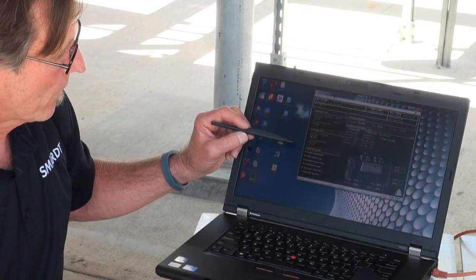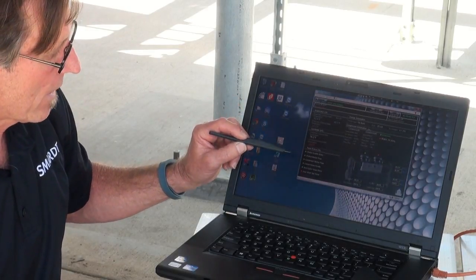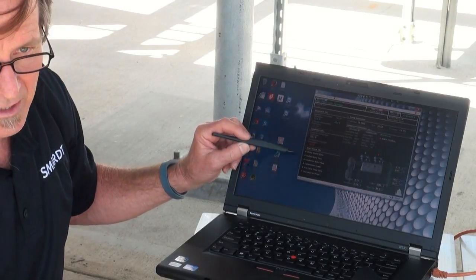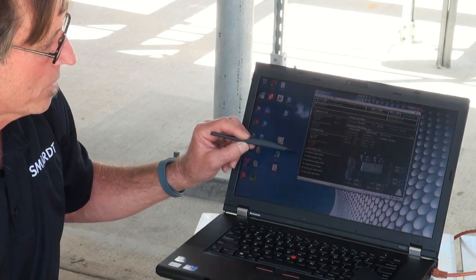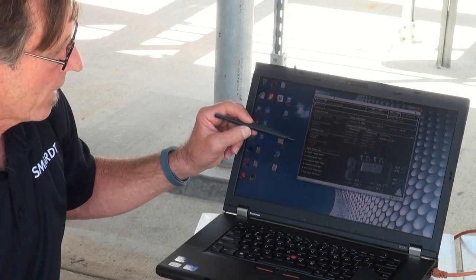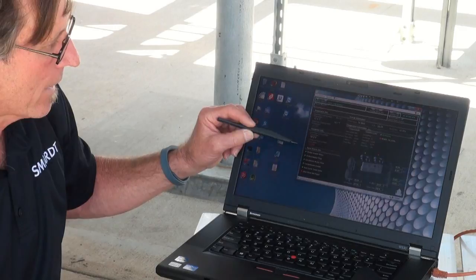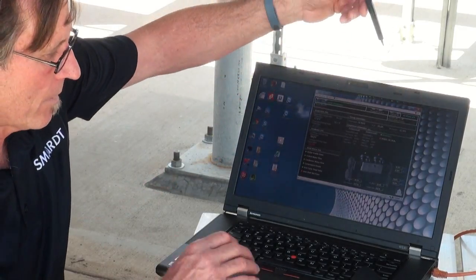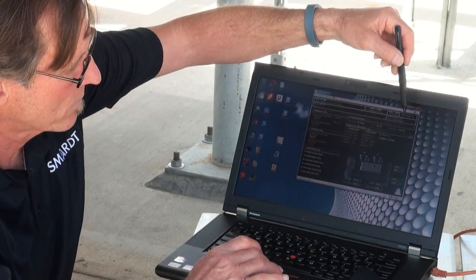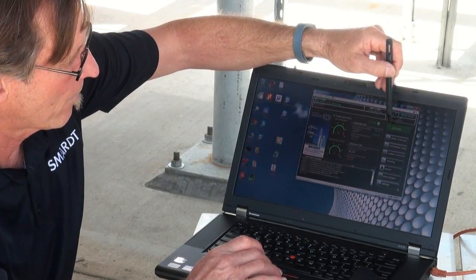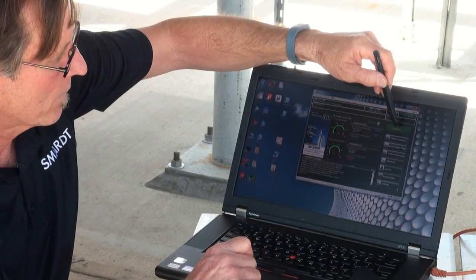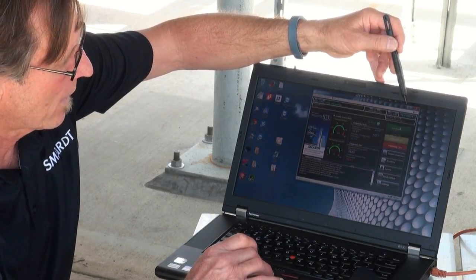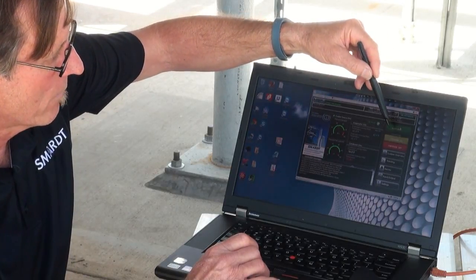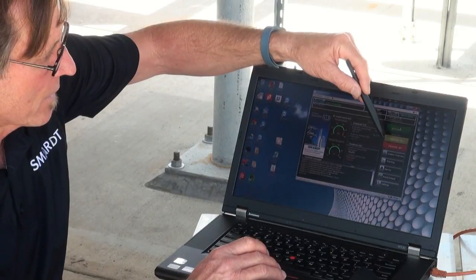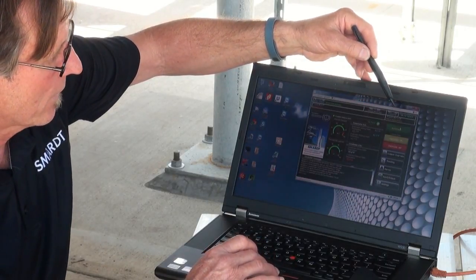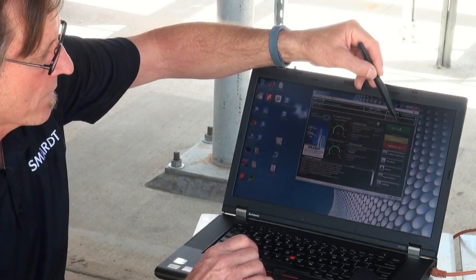If you're fretting about why your chiller's not running, come over here and take a look, and if something's not green here, then that points you in a direction where to look. If you don't have an enabled state, you'll say, well, why don't I have an enabled state? Maybe go back to your home page, and maybe it's not set to auto. You click that, and you see you've got choices. You've got override off or override on. So maybe it somehow got switched to override off, so that's why it's not running. You can always override the BAS system by going override on.